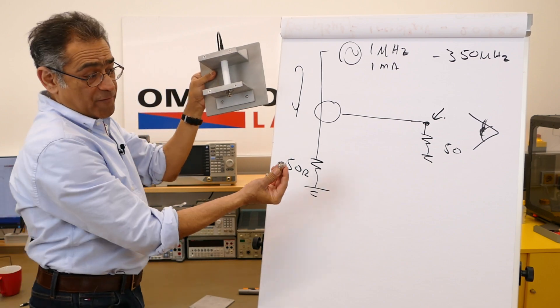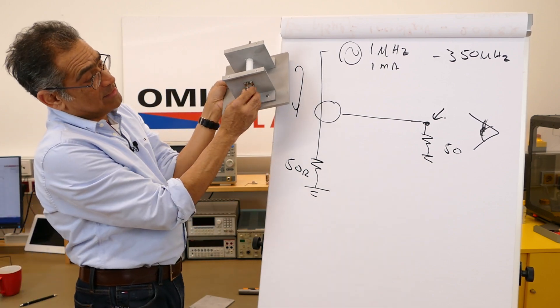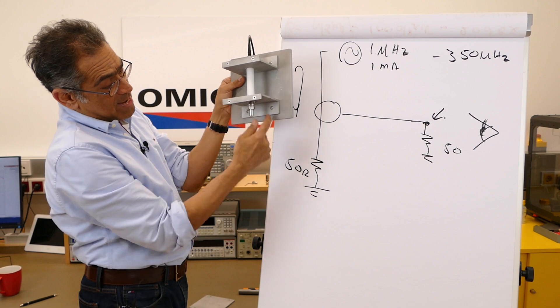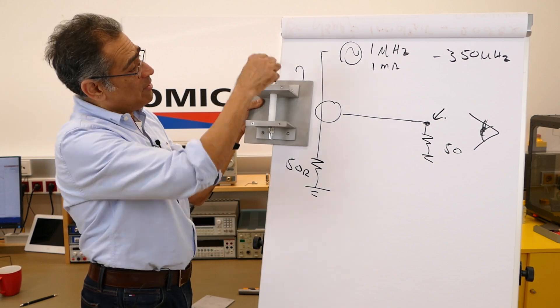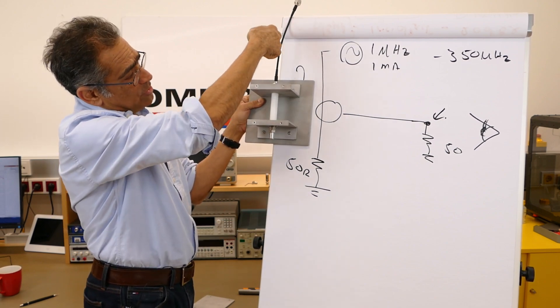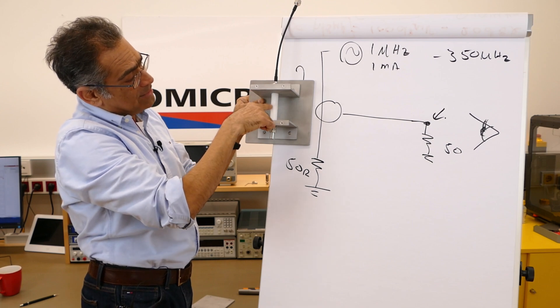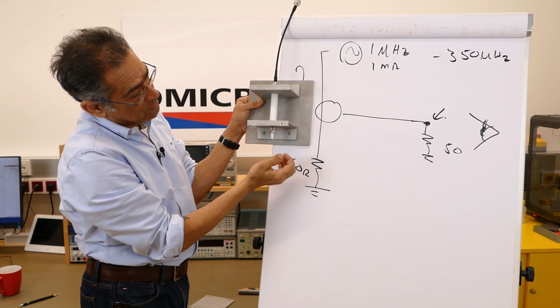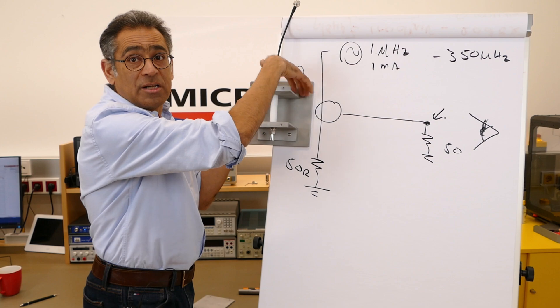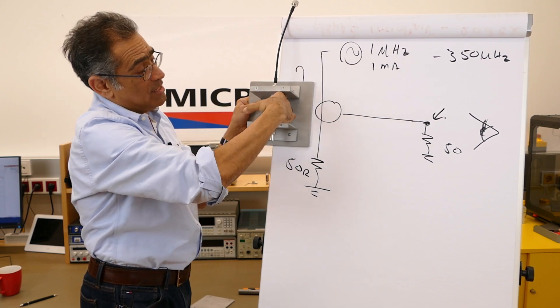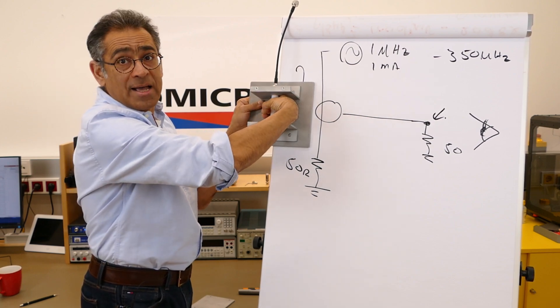And then you have a 50 ohm terminator which sits at the end there, connected to ground. So effectively what is happening is a current is going through here - this is a single cable - goes through the 50 ohm and returns via the metal chassis. And all you have to do then is you clamp your current over here and then you make a measurement.